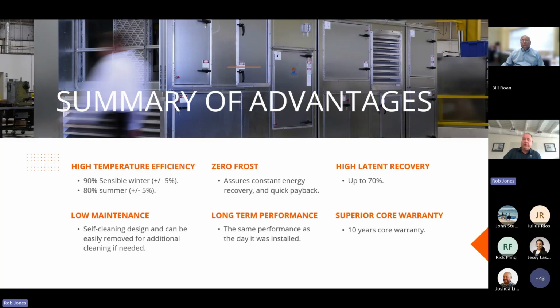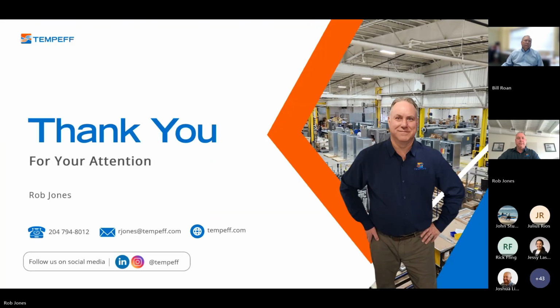High latent recovery of up to 70% with dual core in the winter and with dual core plus 60% in the summertime. Lower maintenance, we're self-cleaning, but the cores can be easily taken out. Long-term performance, we did a third-party study on a 17-year-old installation. It was still running at 90% like day one, and our core warranties are 10 years. They're made out of aluminum. They're hard to break. And with that, I hope I gave you some good insight on what our dual core technology can do. I thank you all for your time, and I'll turn it back to you, Bill.